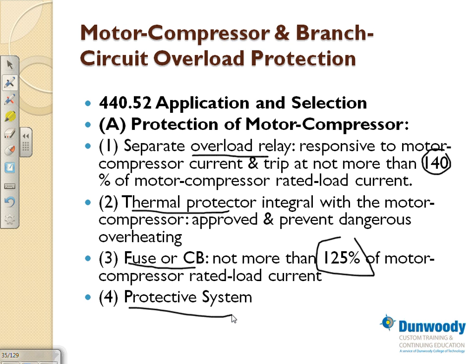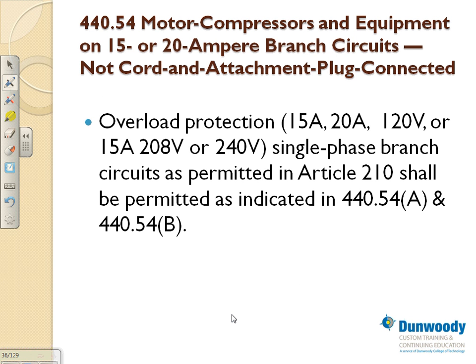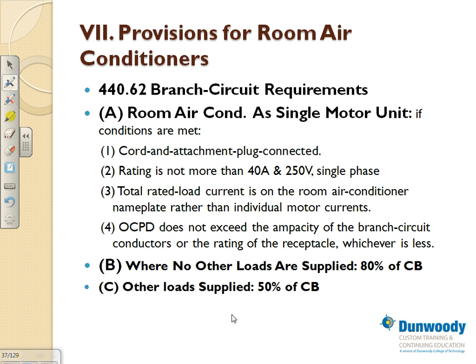Any comments? Any questions? A couple of things about sizing them. If you have equipment, look at the amps. These are smaller equipment, guys. 15, 20 amp branch circuits, not cord and attachment plug connected. The overload, single phase circuit, shall be permitted based on A or B in this one. So basically, the circuit breaker on, look at these systems. They're smaller systems, guys. Single phase first. Then you can see the voltage. They're all single phase: 208, 240, 120. The circuit breaker protects you. Provide overcurrent protection as well as short circuit protection on this equipment.